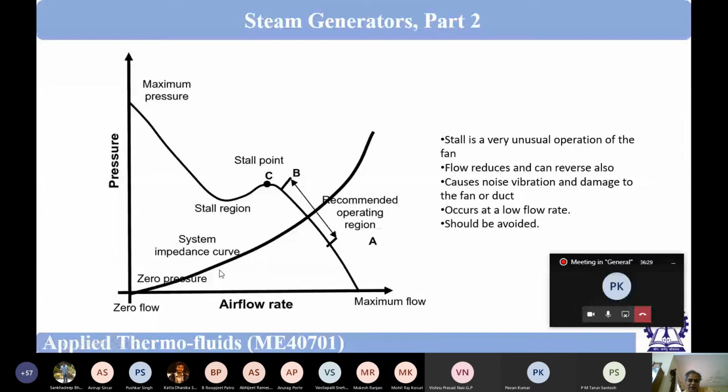So you have got the ducting, you can calculate the resistance, and how the resistance changes with flow rate. So you will be able to find out the operating point, and you will be able to see whether really the duct design and the selection of fan is serving your purpose or not. At the end of the day, this is the kind of necessity when you are designing a typical system. So, up to this, if you have any point, question.